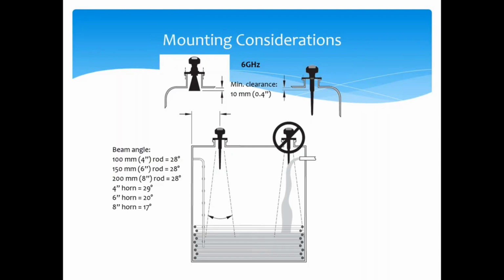Are there any concerns using a radar in an open air application regarding government regulations? Yes, there are. The FCC has guidelines for which you are able to use a radar in an open vessel. It's related to the frequency of that radar and the beam angle as to whether or not it will meet FCC guidelines. I believe for beam angle it's 12 degrees or less, and for frequency I would have to get back to you. I believe we can do the 25 gigahertz or the high frequency radar, but I would need to double check on that.